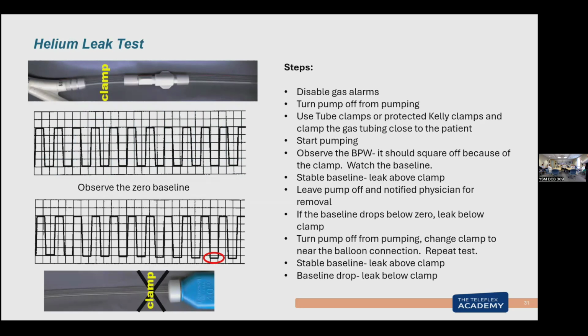Possibly helium loss 2 is if I'm getting most of it back, I'm just not getting all of it back. But I don't see blood in the tube. There's a difference in the drop. I only do the internal leak test when it's a possible helium loss 2, for repeated helium loss 2s.